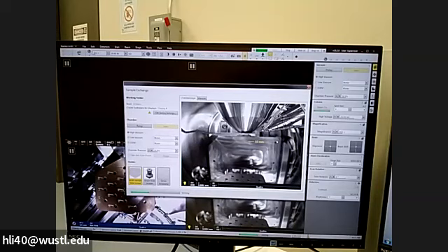After you start the venting process, you can also see the green bar here. The green will progress from left to right. When it comes to around this location, we are ready to open the door. So we just wait. It takes about 3 minutes in total.